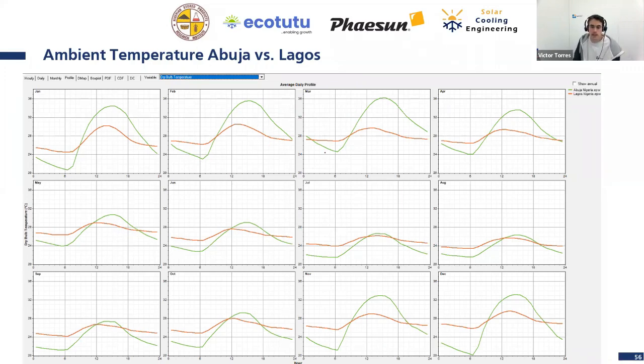Abuja has much higher temperature fluctuations. We see here maximum temperature of 36 degrees in February on average, and 23 at night. Of course you have days with 40 degrees, but this is the average fluctuation between day and night. If we are running our cooling units during solar radiation periods, then in Abuja we will deal with lower efficiency in our cooling units than in Lagos, because the ambient temperature during the day is always higher in Abuja than in Lagos. This we need to consider in our design, so we need to understand very well the weather conditions at the location where we are installing our cold room. It will make a big difference.